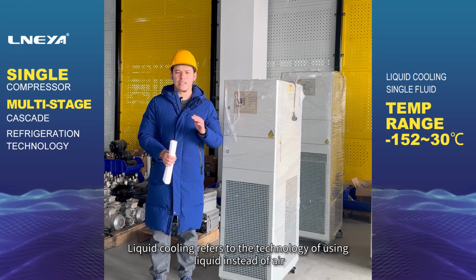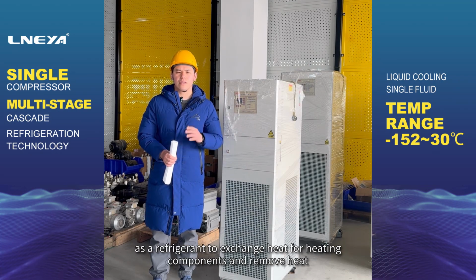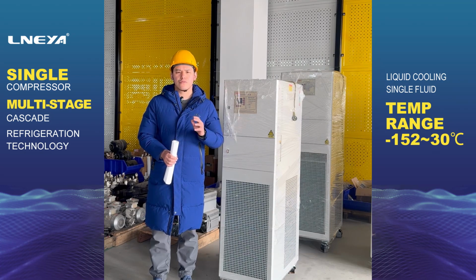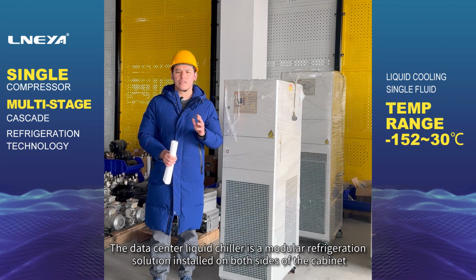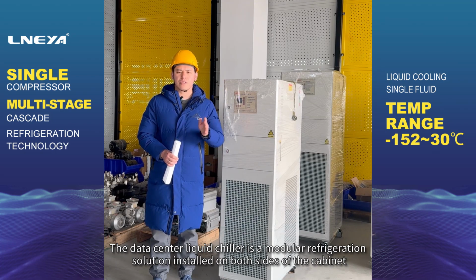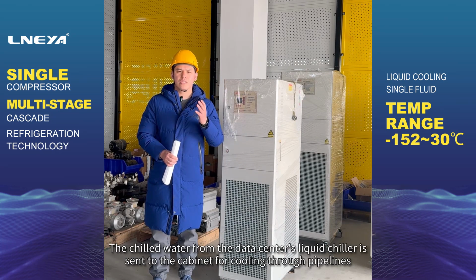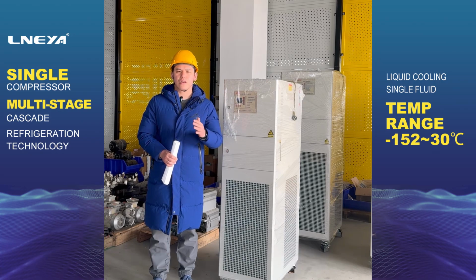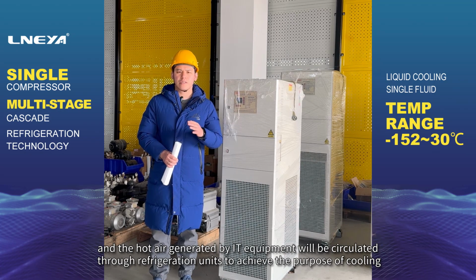Liquid cooling refers to the technology of using liquid instead of air as a refrigerant to exchange heat for heating components and remove heat. The data center liquid chiller is a modular refrigeration solution installed on both sides of the cabinet. The chilled water from the data center's liquid chiller is sent to the cabinet for cooling through pipelines, and the hot air generated by IT equipment will be circulated through refrigeration units to achieve the purpose of cooling.